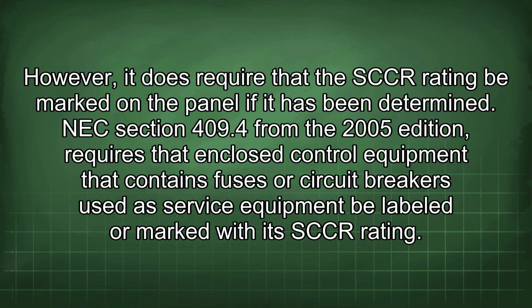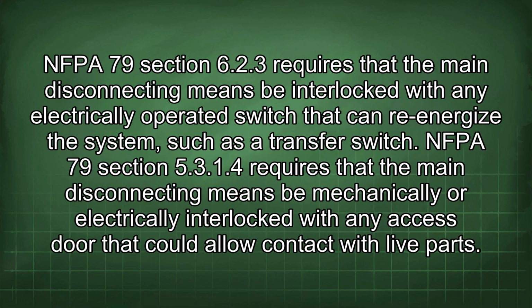NEC Section 409.4 from the 2005 edition requires that enclosed control equipment that contains fuses or circuit breakers used as service equipment be labeled or marked with its SCCR rating. NFPA 79 Section 6.2.3 requires that the main disconnecting means be interlocked with any electrically operated switch that can re-energize the system, such as a transfer switch. NFPA 79 Section 5.3.1.4 requires that the main disconnecting means be mechanically or electrically interlocked with any access door that could allow contact with live parts.